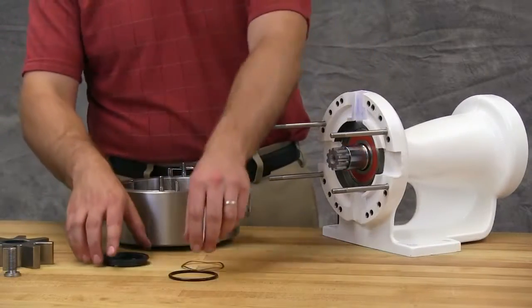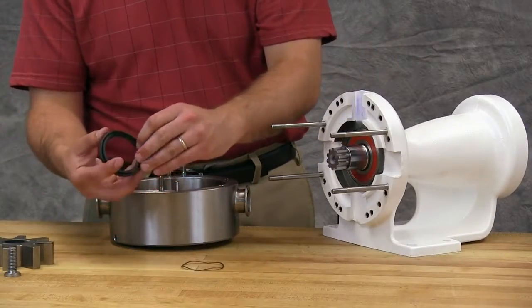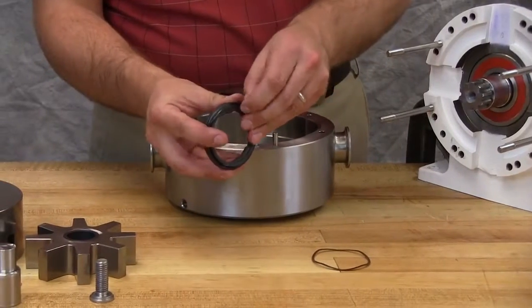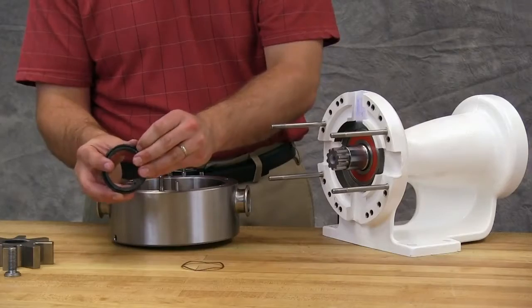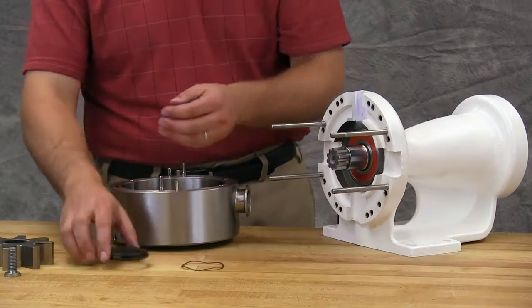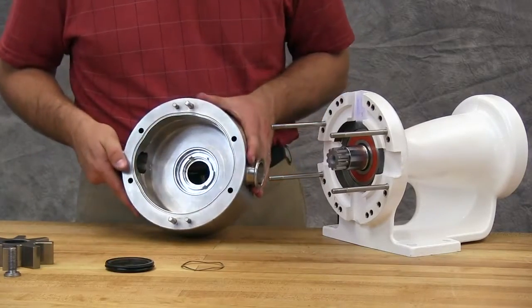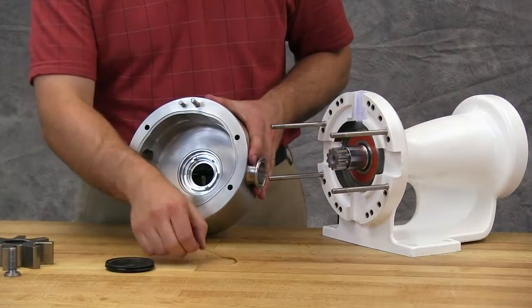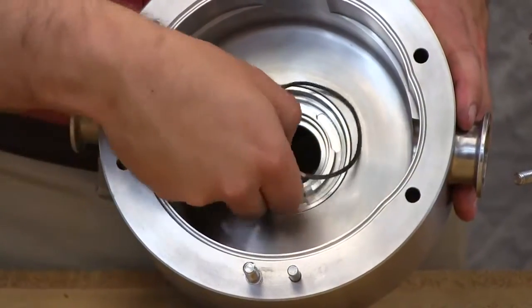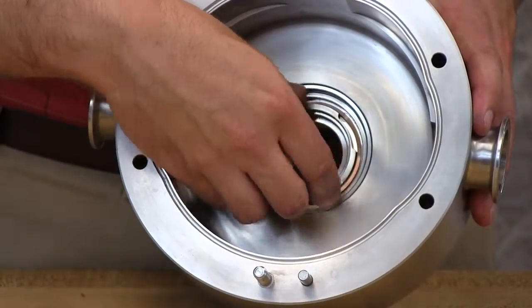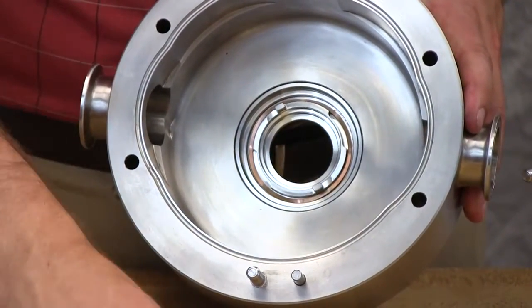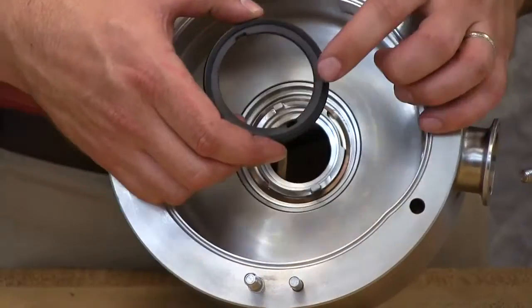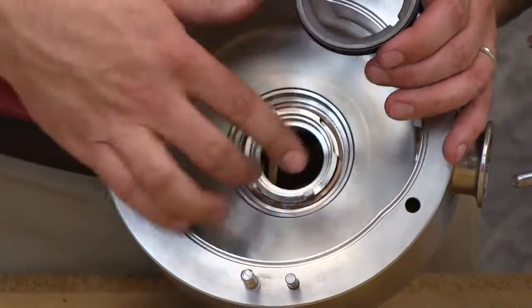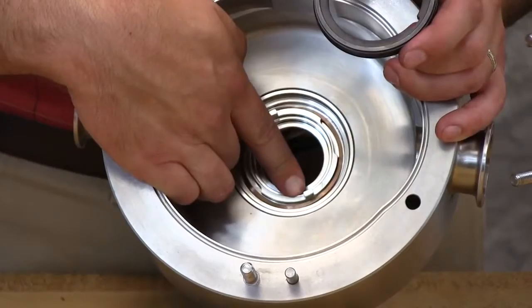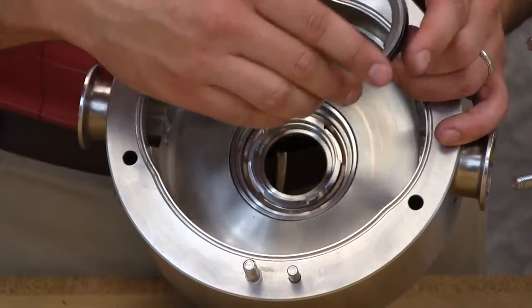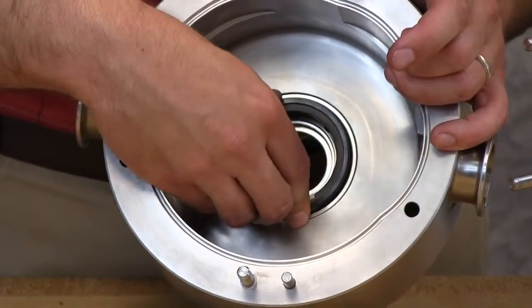Install the stationary face O-ring onto the stationary face. When handling and installing the seal faces, avoid touching the raised sealing surface with anything besides clean hands or a clean cloth. Install the wave spring into the seal housing. Make sure that the notches on the back of the stationary face line up with the tabs on the seal housing. Install the stationary face into the seal housing with the O-ring side facing the back of the casing.